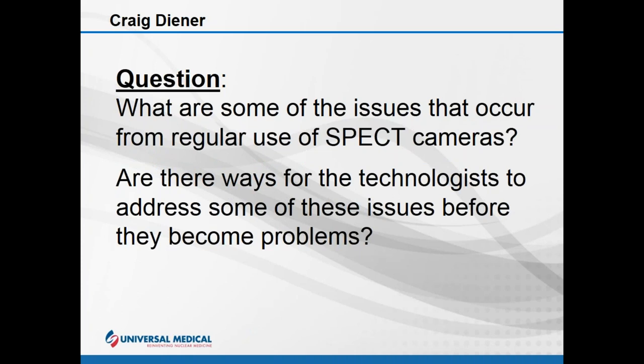Yes, as Nick and Craig both pointed out, there's constant moving parts on these cameras, so regular maintenance is critical. Grease tends to dry out and can cause motion problems, as Nick mentioned. Mechanical parts are cleaned and greased on a regular basis to ensure smooth operation. Heat is the biggest enemy with any electronic equipment, and in the case of nuclear cameras, it can cause tube drift, which results in peak shift and image quality problems.